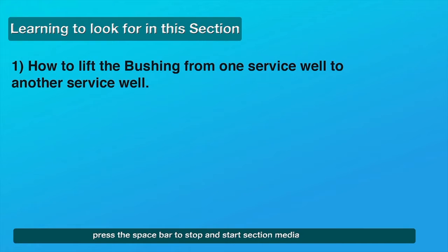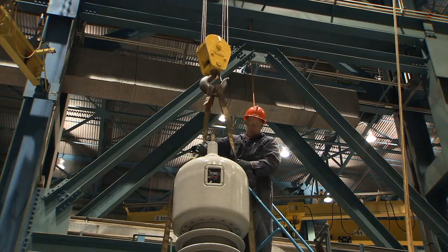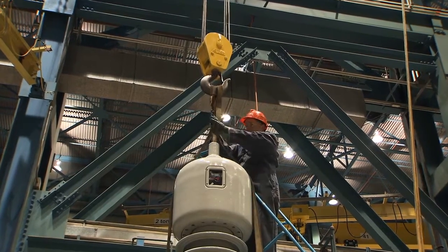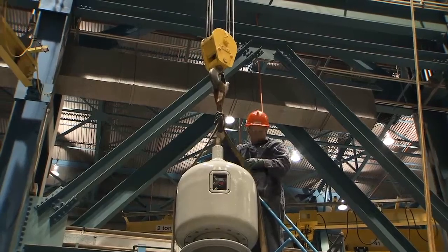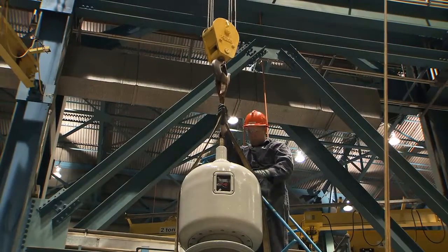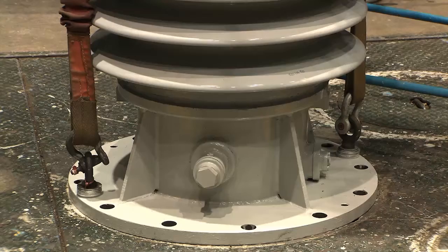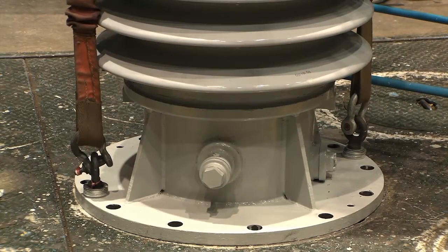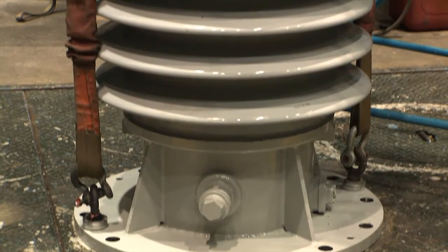Moving the bushing from one service well to another to allow for final electrical testing. In order to move the bushing, 2 slings are choked onto the hoist crane that are attached to the flange. 2 inserts are placed on opposite ends of the flange, and 2 eye bolts are fastened onto the inserts.